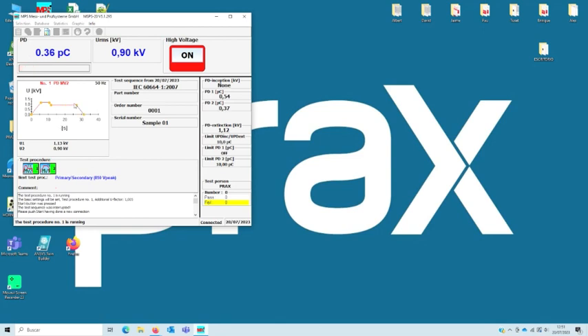So as you can see here, there is no inception voltage because the maximum partial discharge was below 10 picocoulombs, and here is where we define the measurement voltage. Okay, so this part could assure a maximum working voltage between primary and secondary side of 850 volts.